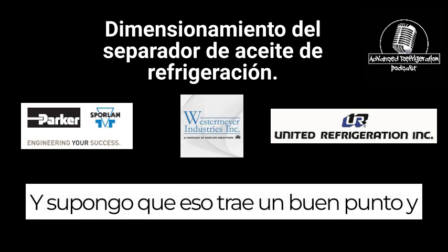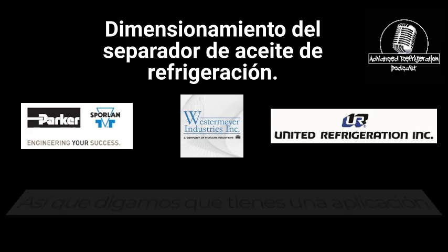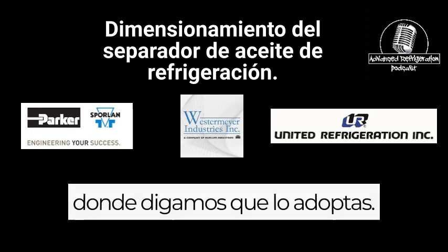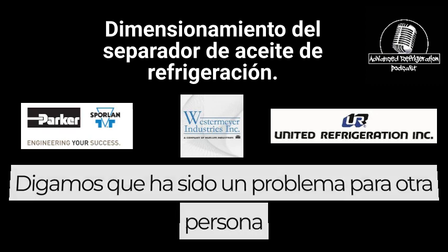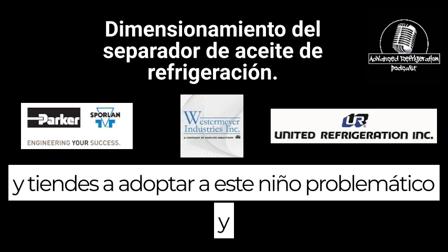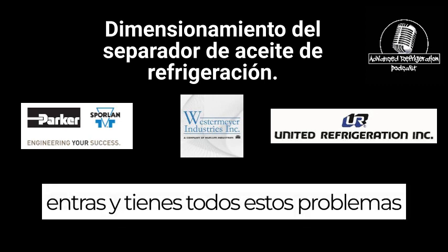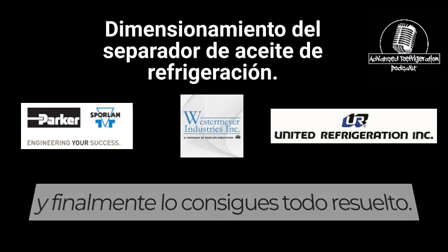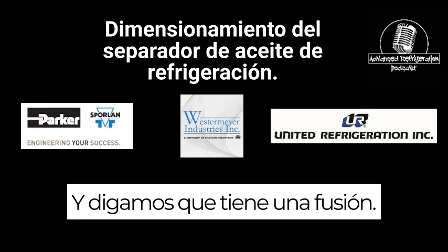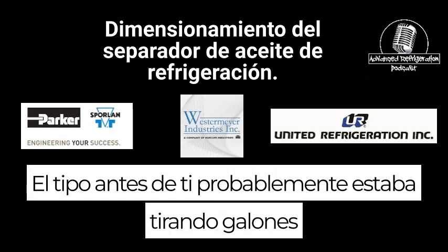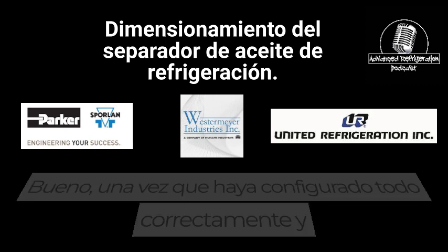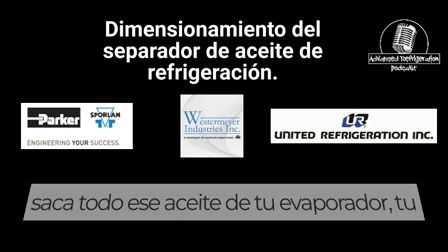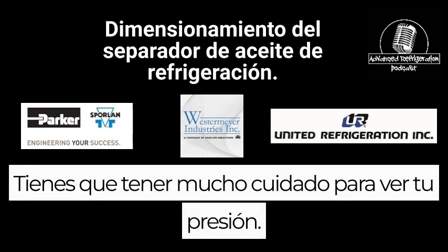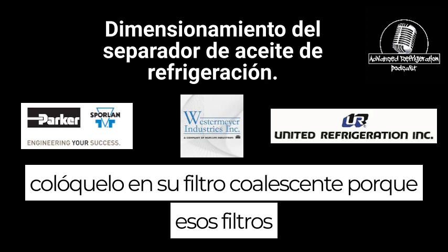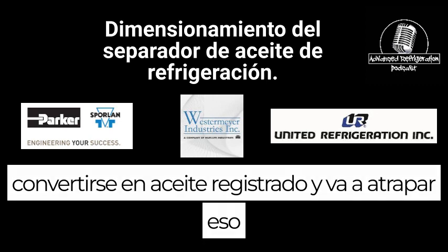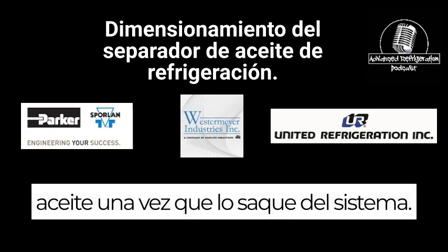Well, I guess that brings up a good point, and something that I think also needs to be mentioned. Let's say you adopt an application that's been a problem for somebody else, and you walk in, and you've got all these problems, and you finally get it all worked out. And let's say it's got a coalescing filter on it. The guy before you likely was dumping gallon after gallon of oil inside that system. Well, once you get everything set properly and you get all that oil out of your evaporator, you've got to be very careful to watch your pressure drop on your coalescing filter, because those filters will become oil logged, and it's going to catch that oil once you get it out of the system.